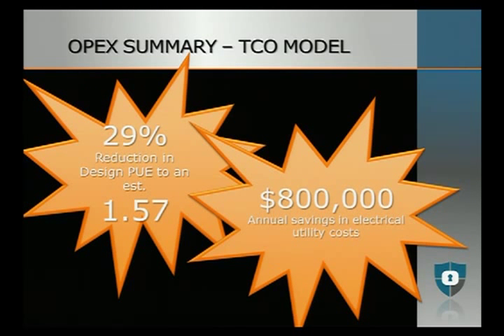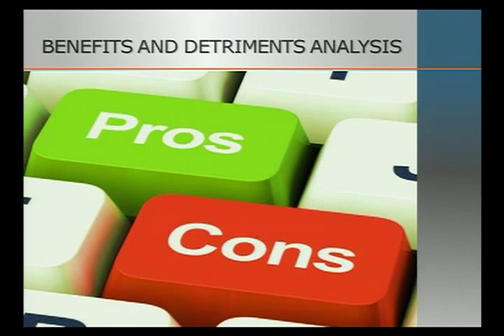We were going to be able to reduce the PUE from 2.2 down to 1.57, a 29% reduction. And back when we put that goal of 30% in there, I thought there's no way. If we get halfway there, we've done something. $800,000 in annual power savings that we should see once the design is completely put in and the loads are there.